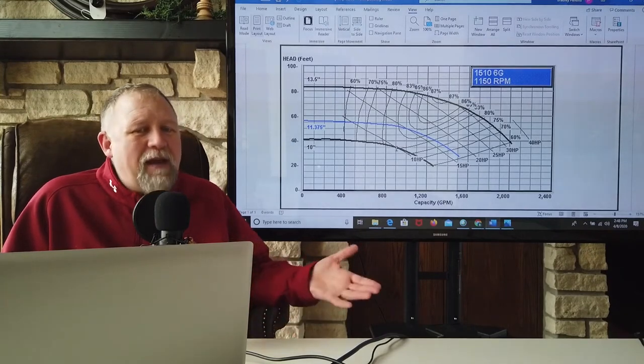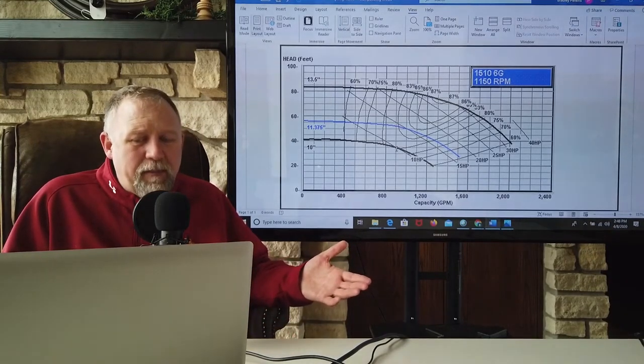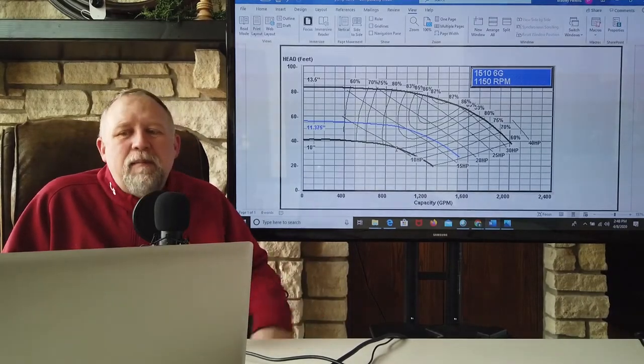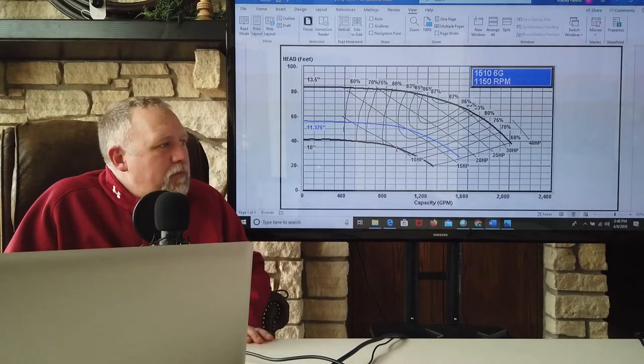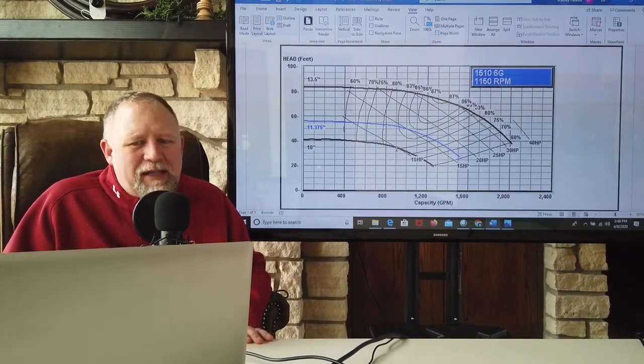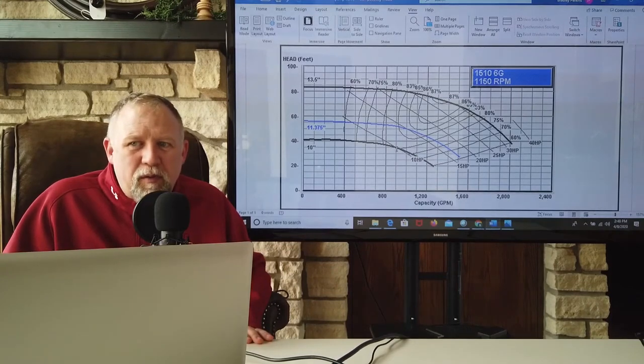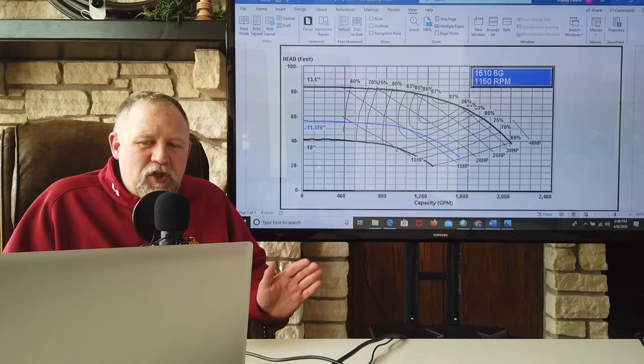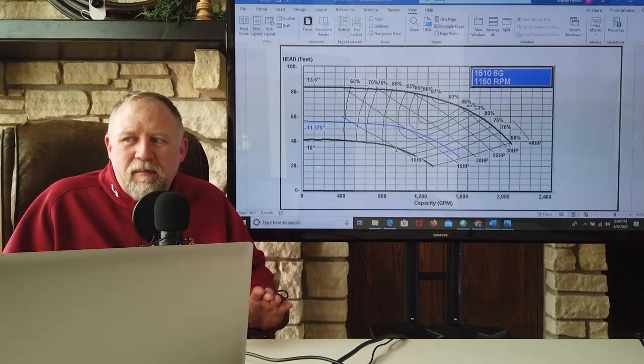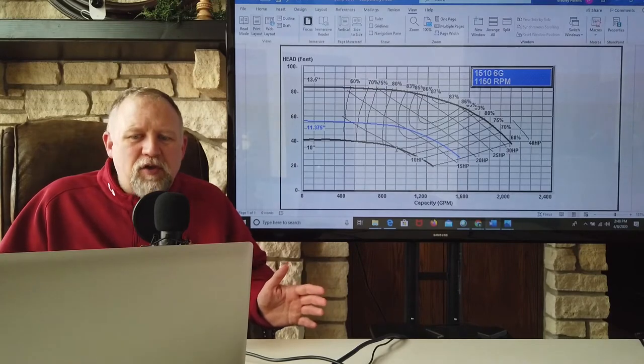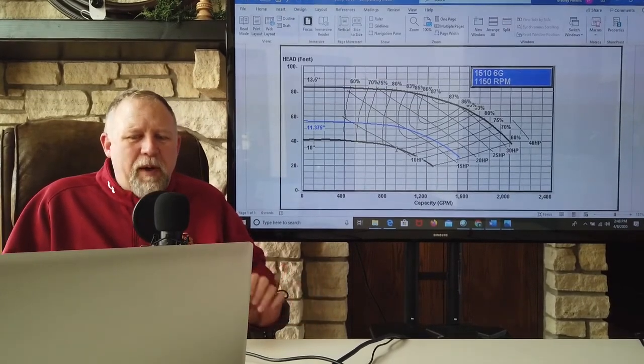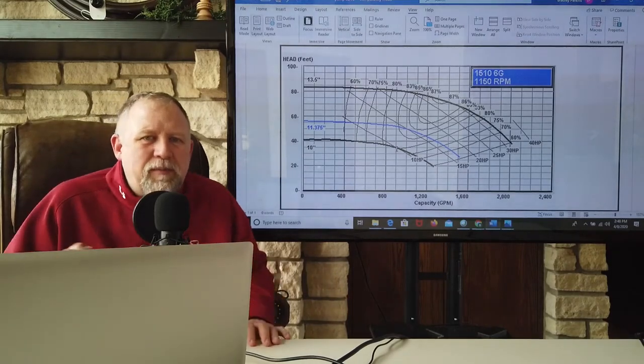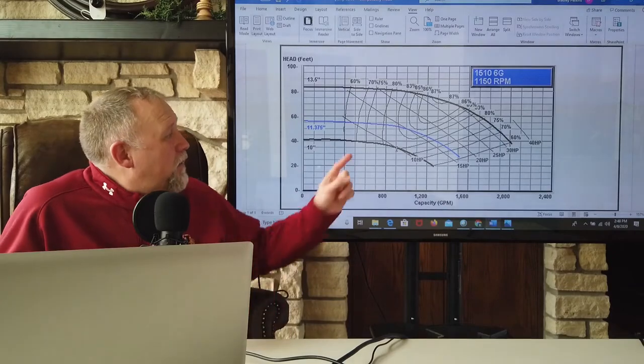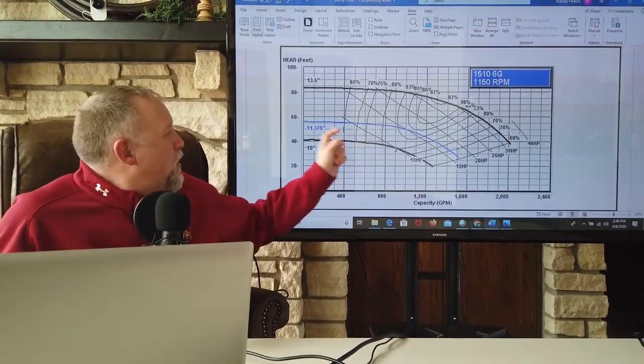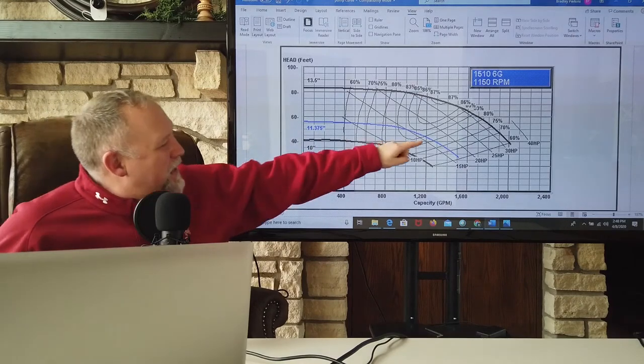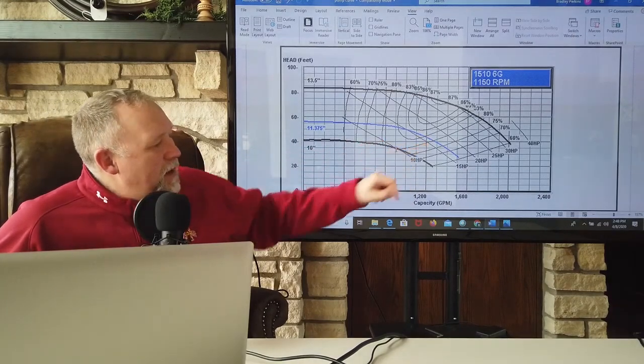During the design phase, you're going to have to make an estimate of what you think that resistance to flow is going to be. Most likely, most engineers, if they're cautious, are going to overestimate the pressure loss through their system. In other words, if you've got to choose between being high and being low, you say, well, I'm going to overestimate the pressure drop through this pipe so that I know I have enough pump capacity. A reasonable assumption. However, when you do that, your actual operating point will go towards lower head loss and higher gallons per minute.